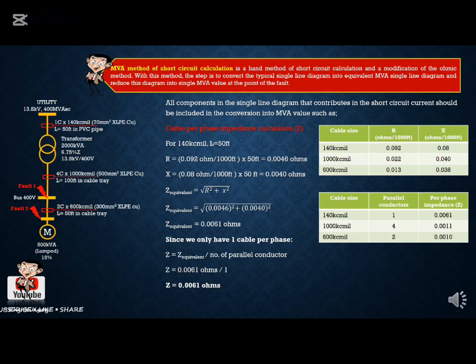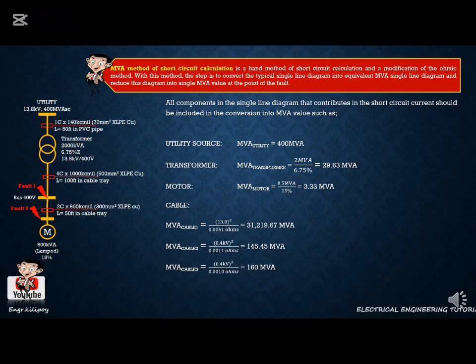So kinumpit na natin yan. For 1,000, ito yung value ng kanyang per phase impedance, 0.0011. And for 600 kcmil, which is 2 core per phase, equivalent to 0.0010 ohms. So ibalik natin yan sa formula ng conversion ng MVA para sa mga cable. So ito yung value niya.